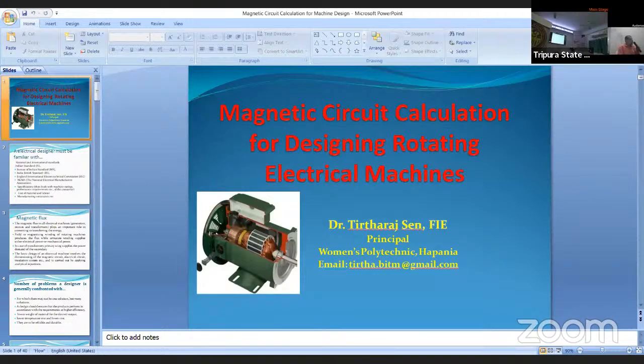Now about saturation: higher flux density reduces the volume of iron but drives the iron to operate beyond the knee of the magnetization curve, in the region of saturation. This magnetization curve is called the B-H curve, flux density versus AT, where AT means ampere-turns. Whenever we wind some windings with some current flowing through them, that is called AT.